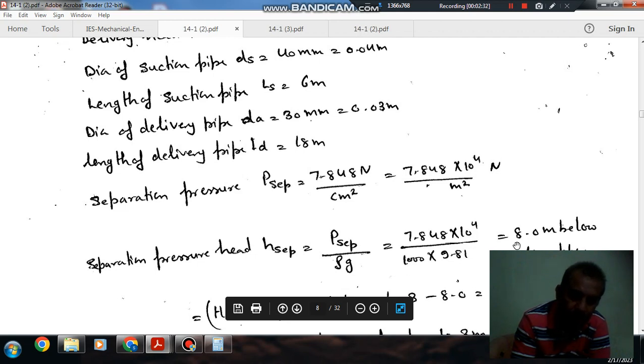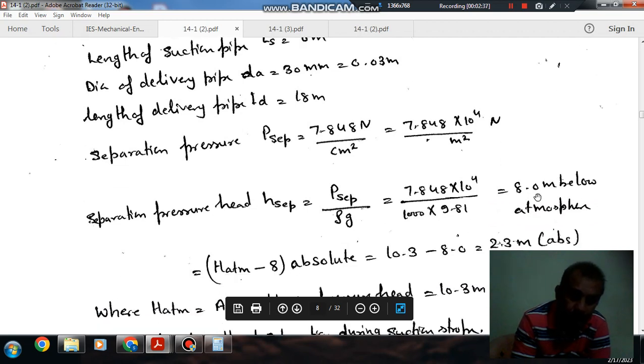So separation pressure will be 8 meters below the atmosphere. Since this is below atmosphere, absolute will be atmosphere minus this 8. So atmospheric head is 10.3 and this is 8, so absolute pressure is 2.3 meters. That is your separation head.